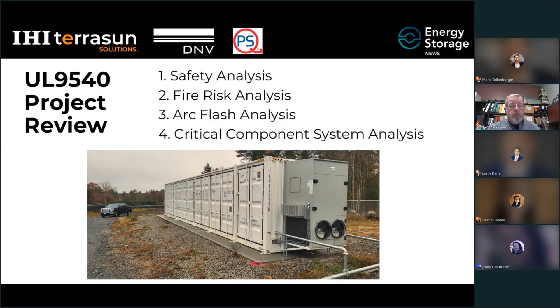UL 9540 also has installation, commissioning, operating, and maintenance instructions that must be included, and that's all reviewed as part of the certification or field evaluation of the energy storage system. We would review the commissioning and decommissioning documents that are included with the installation instructions, the complete installation instruction, initial acceptance testing and procedures that are provided, and ongoing inspection and testing procedures. Instructions for retrofitting system components would need to be included, as well as instructions for providing working clearance, and this would be outside of the energy storage system.